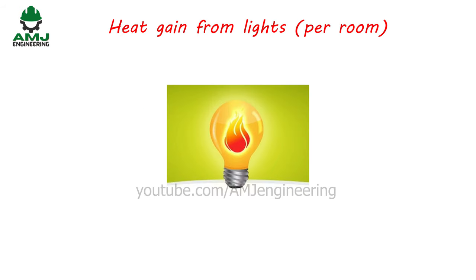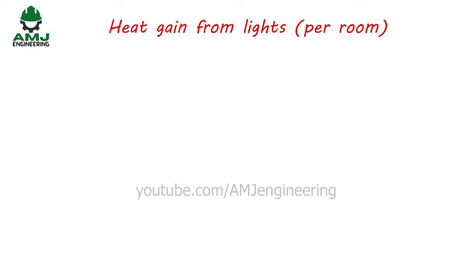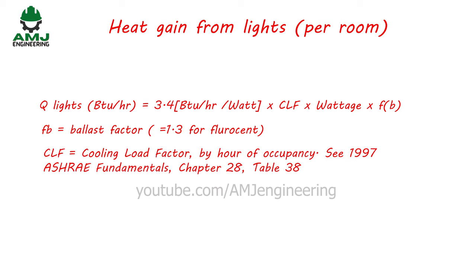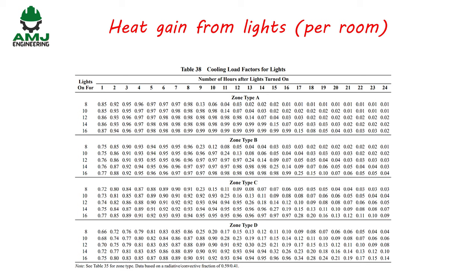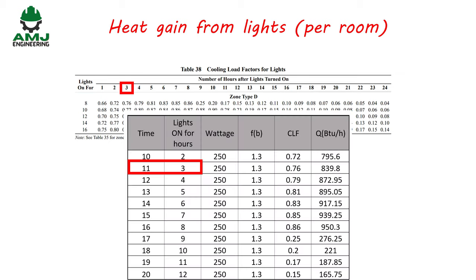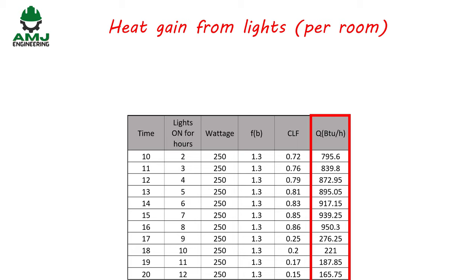The next step is to calculate heat gain from lights using: Q_lights = 3.4 × CLF × Wattage × Ballast Factor. The ballast factor is 1.3 for fluorescent lights. CLF is the cooling load factor by hour of occupancy, taken from Chapter 28, Table 38, for Zone Type D. For 8-hour duty, CLF values are read based on hours after lights are turned on. The total heat gain from lights per room is then tabulated.